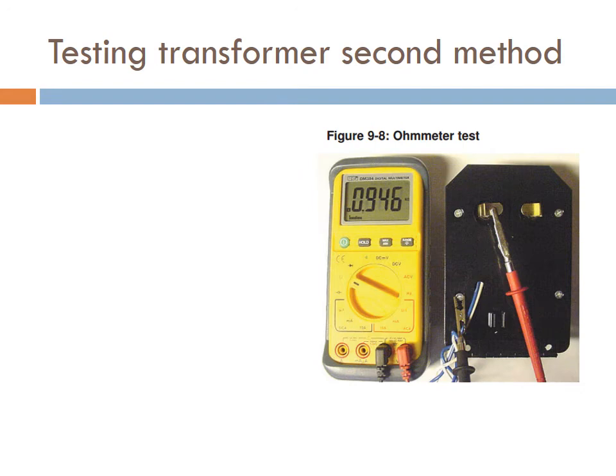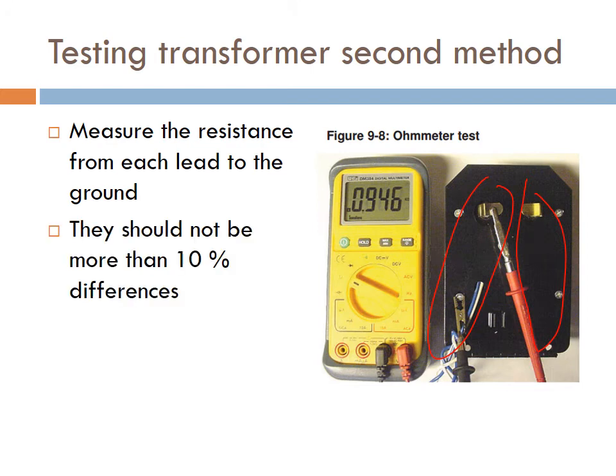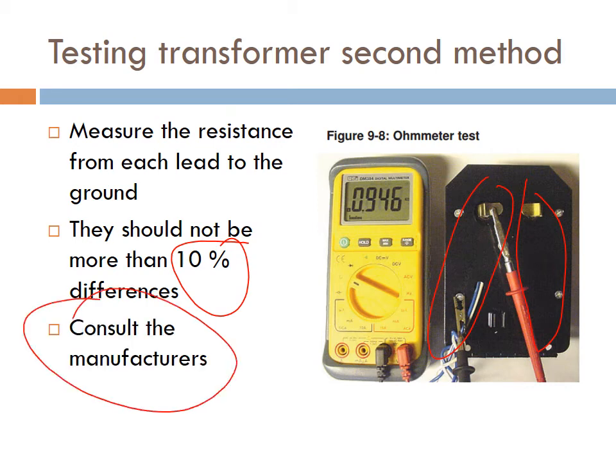Going back to testing a transformer, another way to test a transformer, the one with the winding, is to test the resistance between each one of those prongs. If you see here, we are grounding and testing the resistance. You'll measure the resistance from this prong and the ground, and this one and the ground, and they should be within 10% of each other. If there's a big difference, then something is wrong with that transformer and you have to change it. It will still work, but it's not going to give you enough voltage. Again, you can consult the manufacturer if it's a new transformer and see how they can test it, and sometimes they will just take it and replace it for you.